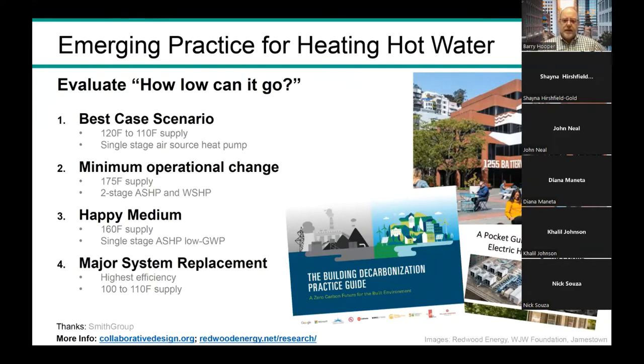One theme from these smaller and medium-sized projects is questioning the assumption of needing 180 degree hot water if that's the existing condition. A growing movement of engineers are asking, what water temperature do we actually need? How low can we go? Because lower temperatures provide a lot more options in terms of which heat pump might be suitable, and that affects both gross electric consumption and space constraints.